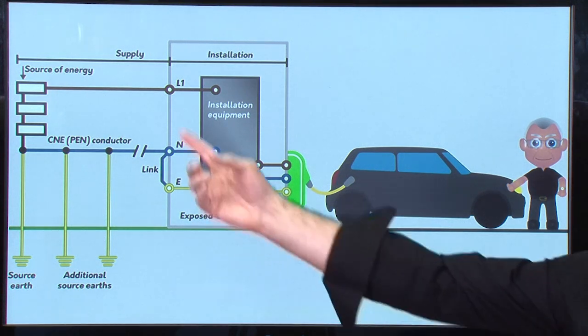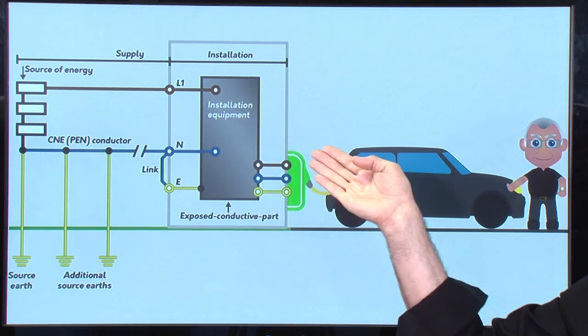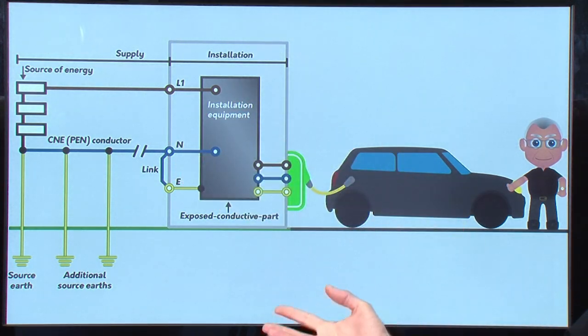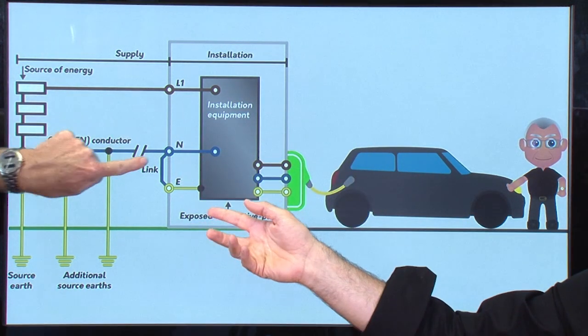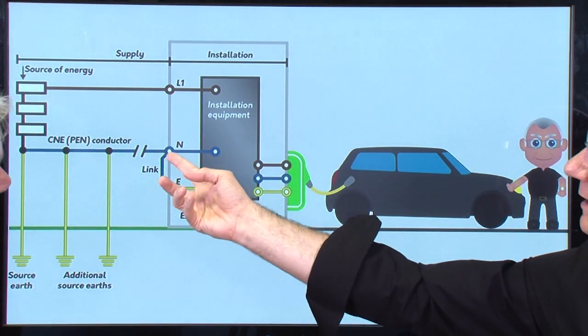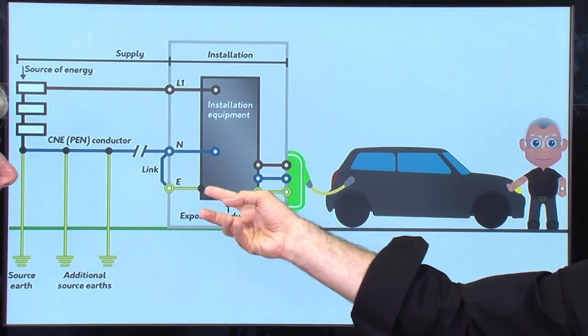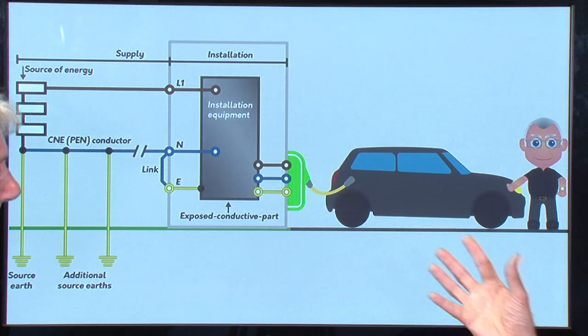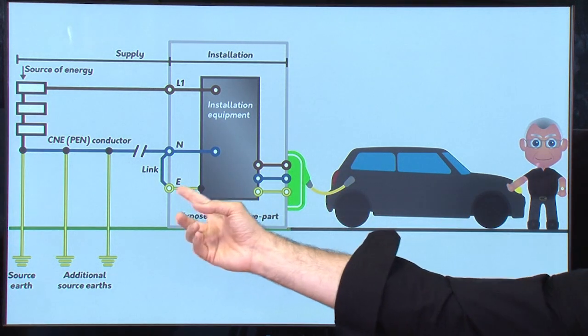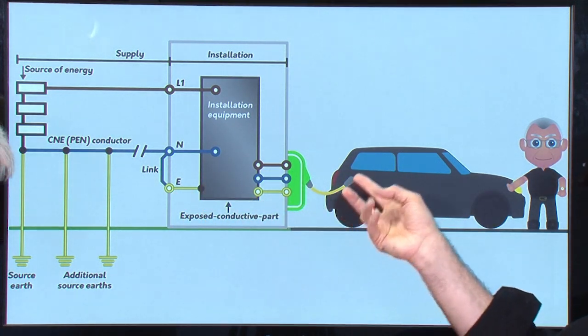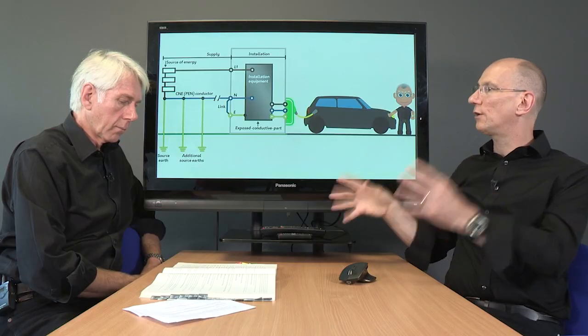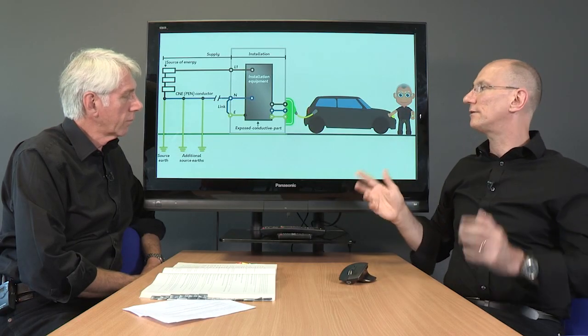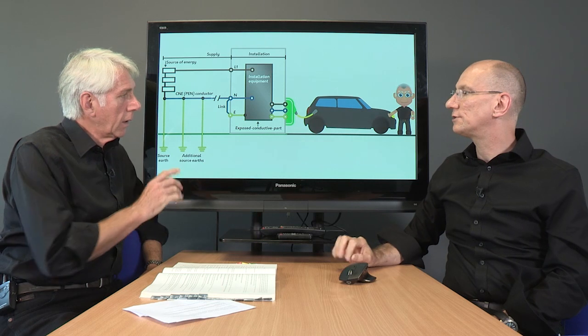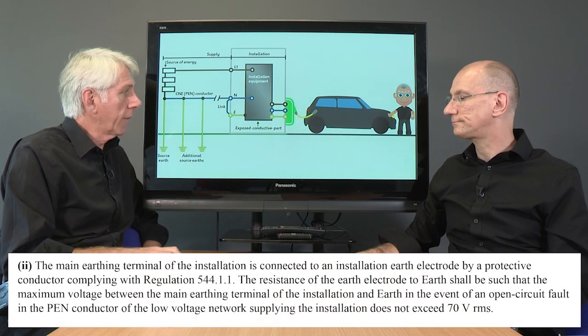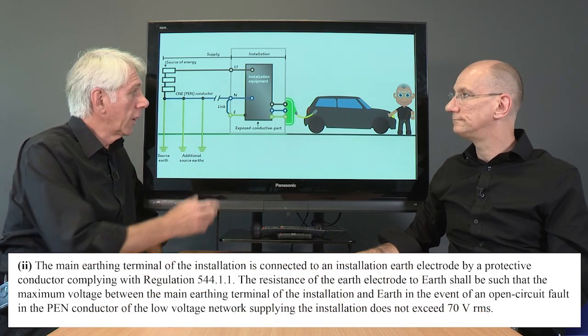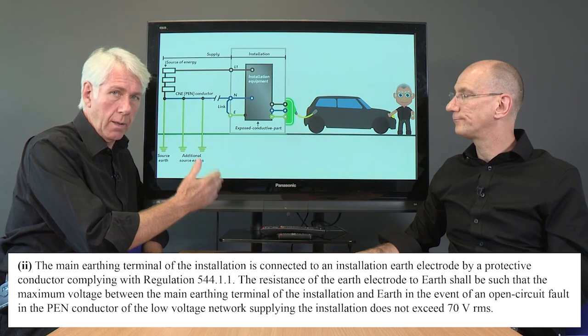Yes, it does. Basically, you have your supply coming in and it would return on the neutral, but if you have a break on the supply cable, it would come back, hit on the link, and then pass through and try any other route to return back to that transformer. And because this is connected and electrically passed through, the vehicle would be charged, and if somebody was in contact with that, an earth and or another earth, you could end up with a fatal electric shock. So the suggestion in this paragraph is that to mitigate that situation, there would be a supplementary earth electrode.